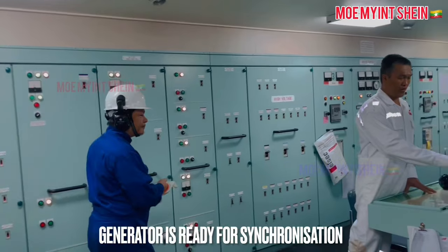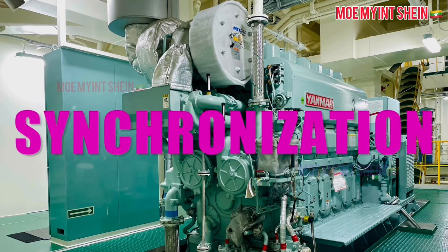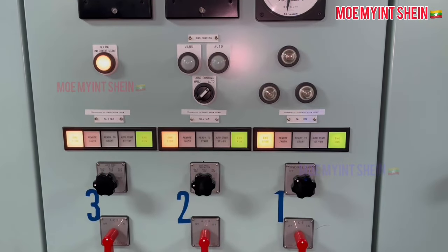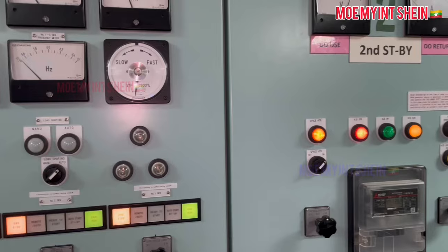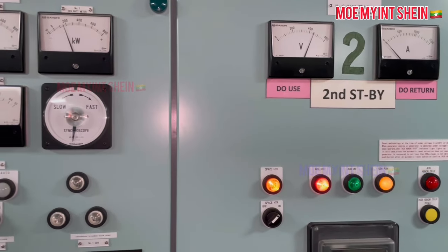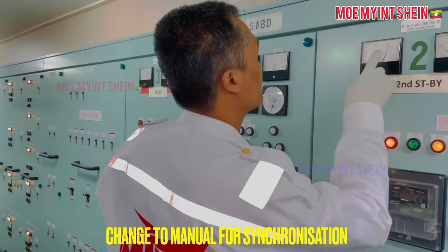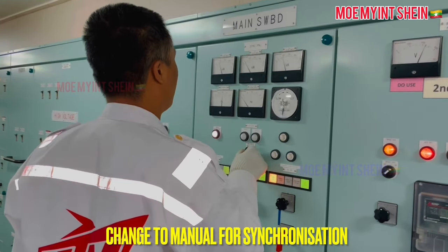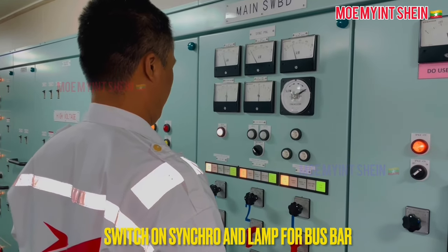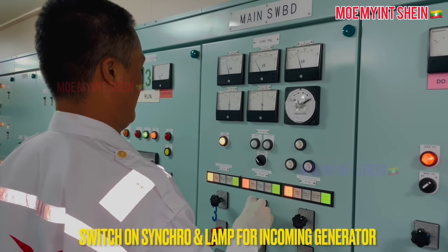Now the generator is ready for synchronization with the bus bar. In this video, I will show manual synchronization. First, change to manual load sharing. Switch on the synchro and lamp switch. After then, turn the selector switch to the incoming generator.